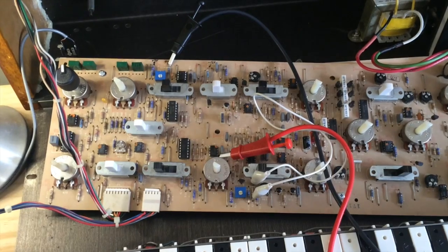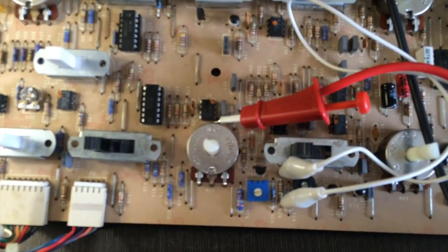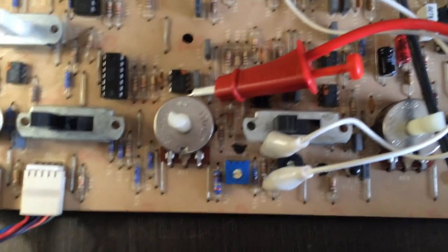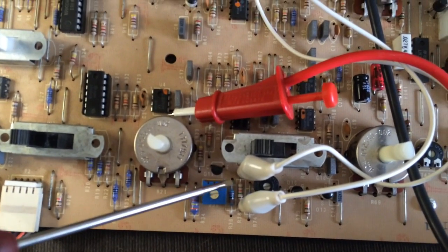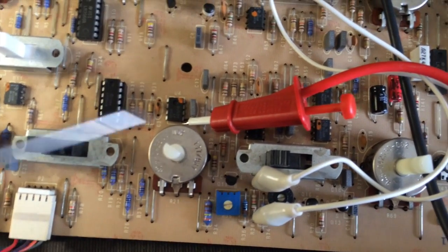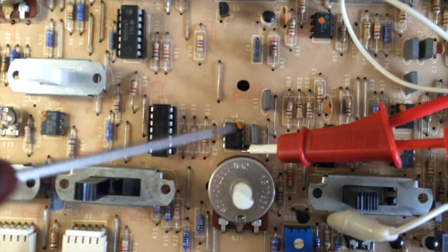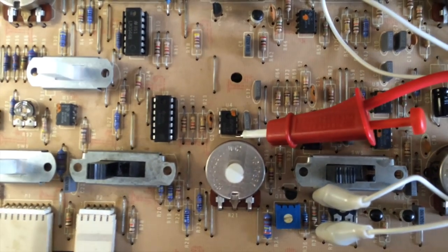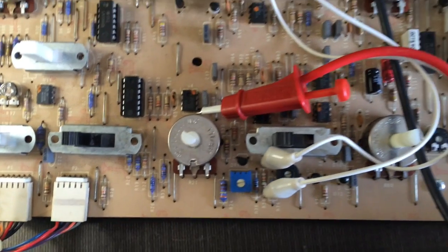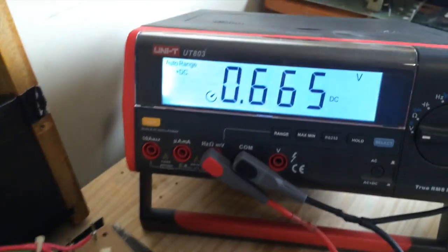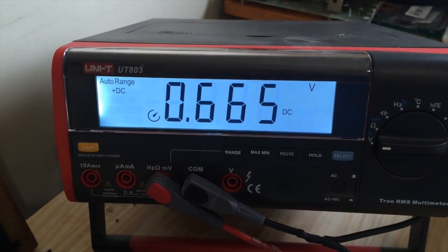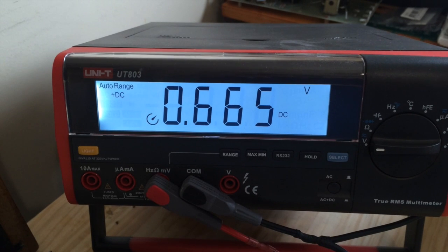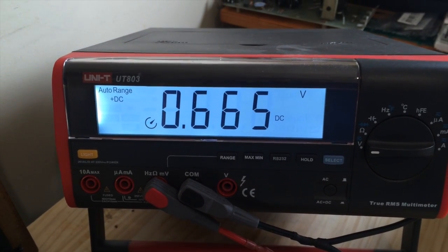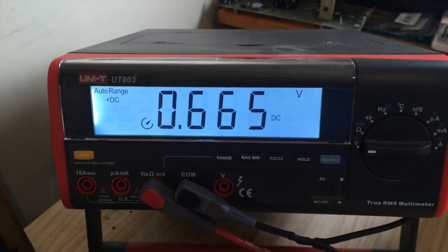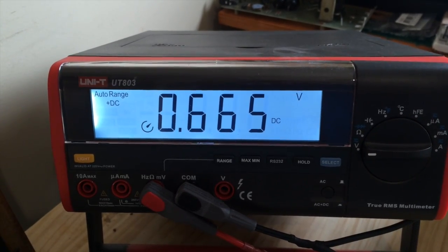Okay, now for oscillator 2, so it's the same adjustment, we're just doing it in different places. So the short now occurs over R38 and the probe we're measuring pin 5 of U4. So the meter is 0.665, so I need a drop of just over 60 millivolts because my room temperature is lower than 22, so probably aim for about 0.602.